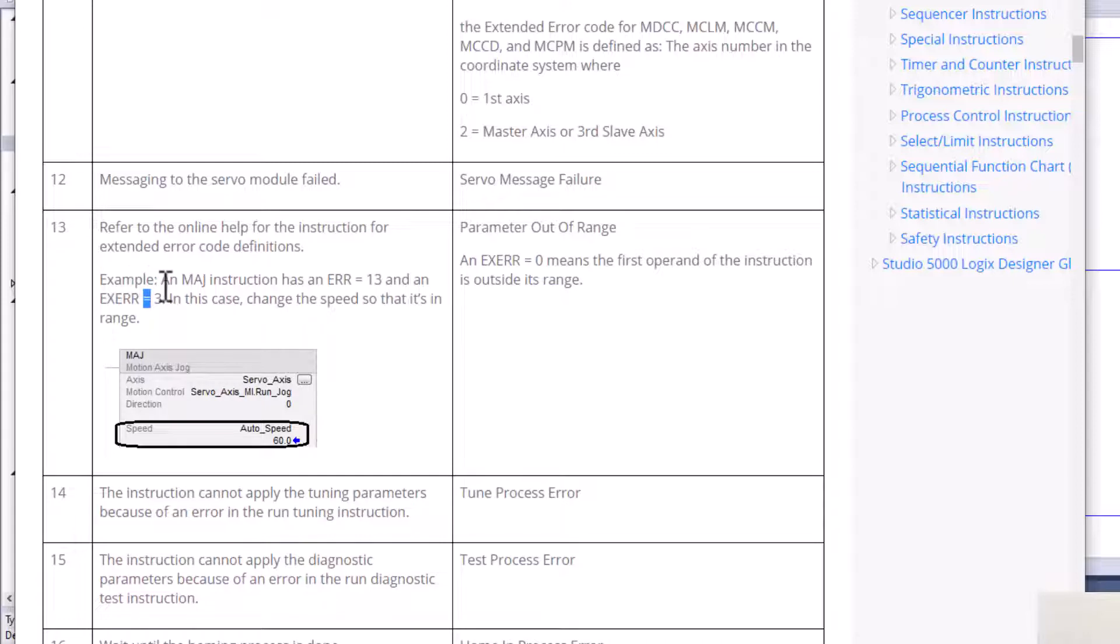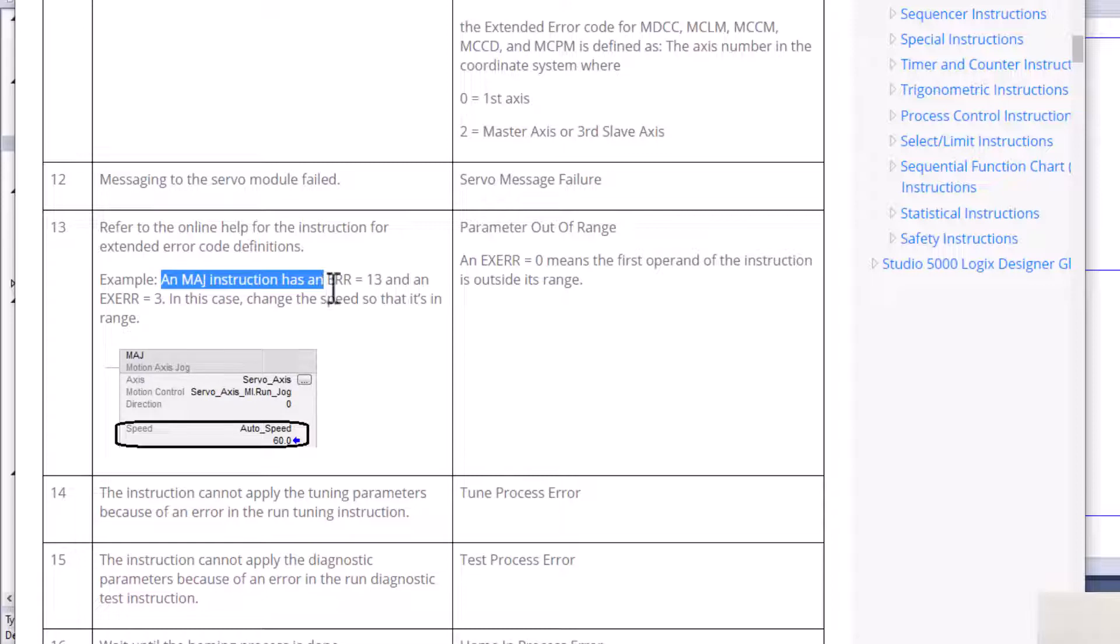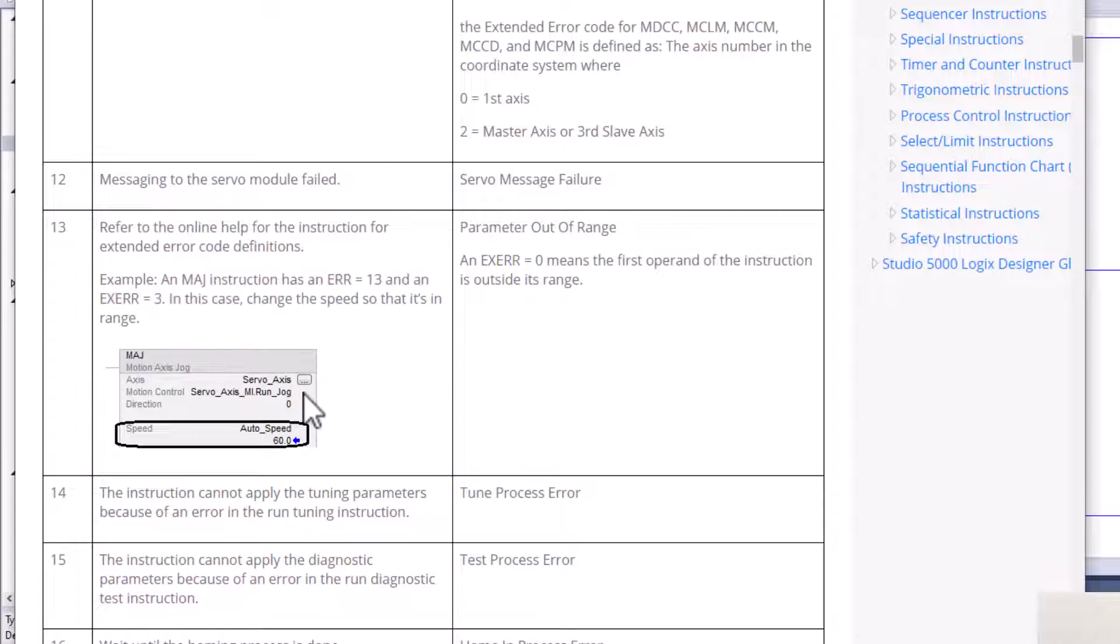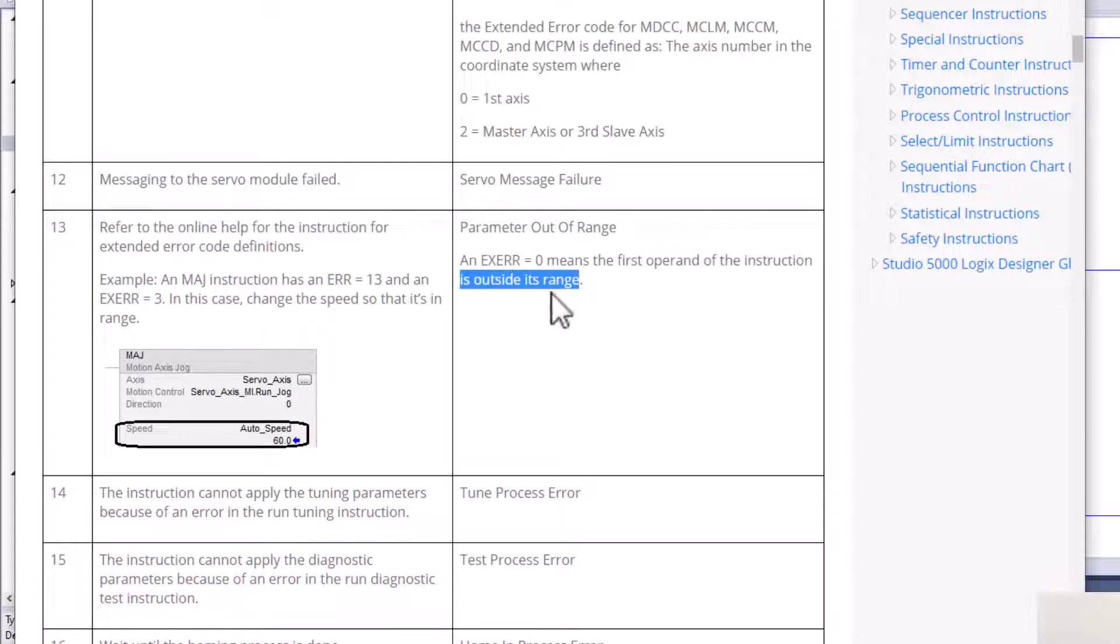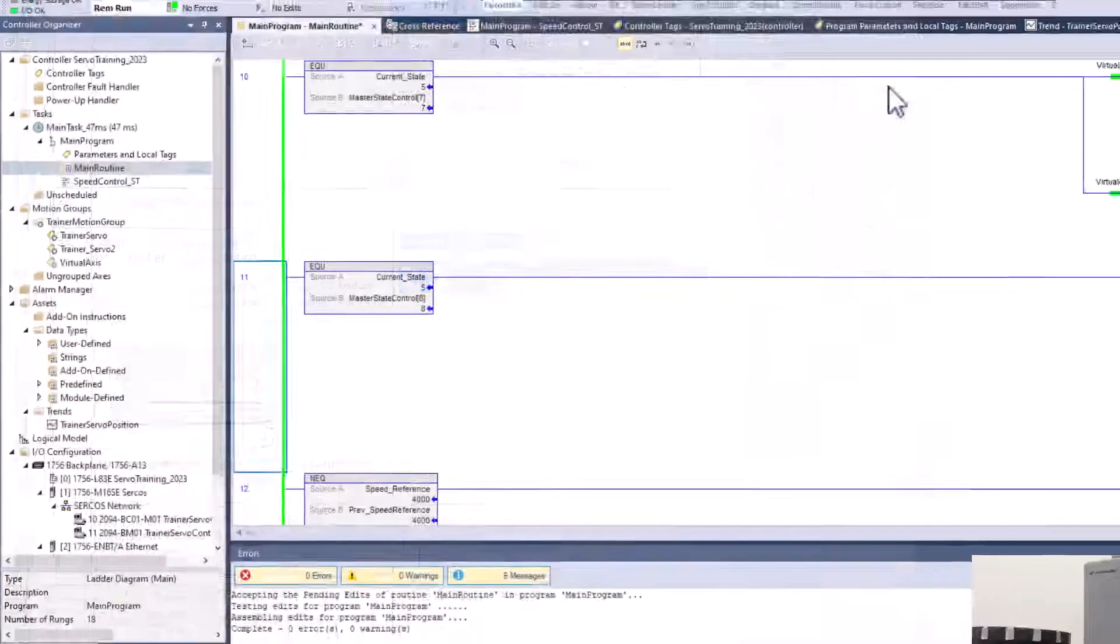So an example they gave you is if you're using MAJ and you have a 13 and extended error of 3, which is not what we're doing. We're doing a position cam, right? So Motion Axis Position Cam. In this case, although if you do have an MAJ and you're running that and you do have an extended error of 3, it's just probably your speeds that are out of range. Then you could fix that really simple. Now the extended error of zero, this means that your instruction is outside of its range. Now this is kind of vague. You think they would show a lot more than this, because the exact error that I had, I'll show you this.